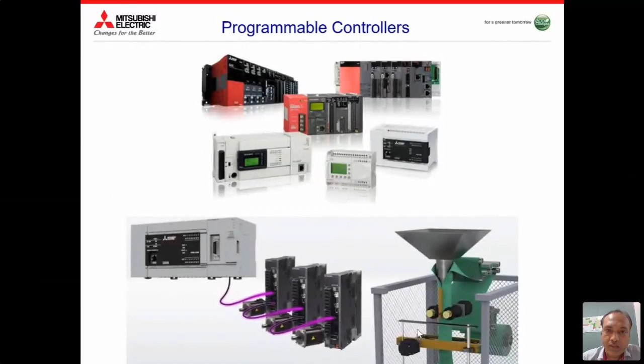Here you can see different kinds of images of PLCs, from micro PLC to modular PLC. Micro PLC is a standalone single PLC with fewer inputs and outputs. So we can start from 10 inputs and outputs till the modular PLC, which can handle 8,000 IOs. This is the selection criteria, how we select the PLC normally: how many inputs and outputs there are, memory, special IO modules if they need to be connected, scan time of the system, which is very important, the performance of the PLC, the communication connectivity, and the software requirement. These are some of the guidelines to select any PLC.